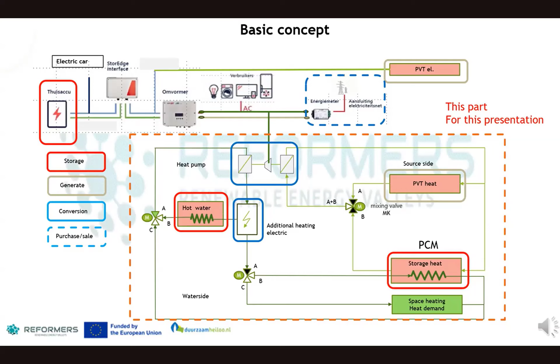The PCM and tap water tank are storage for heat, where this presentation is focused on the heat pump in relation to the heat part of the PVT and the PCM tank, indicated in the red dotted part in the sheet. We start when the heat pump can simply run based on the supplied temperature of the PVT panels. The PCM heat storage is full, and the PVT temperature is below T maximum allowed for the heat pump. There is, for example, a demand for tap water.